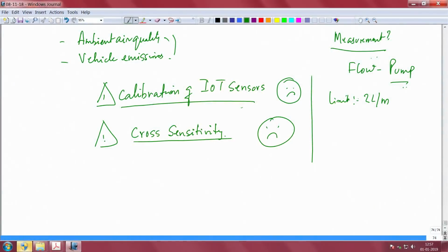This is a dicey question. Some people have said the air flow should not be greater than 2 liters per minute - that's the limit. But typically, when you do a measurement, they use 1 liter per minute, and in fact less than that, typically 0.5 to 0.8 liters per minute should be flowing across these sensors, in order to ensure a proper measurement.